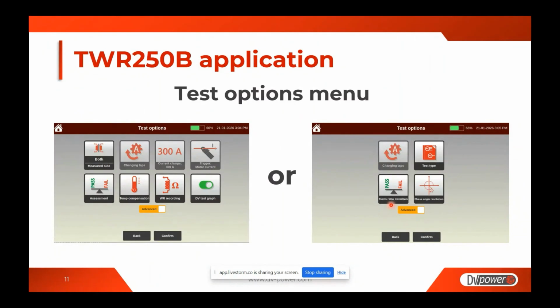On the left-hand side, you can see the display related to test options menu for winding resistance measurement, where you can select if you want to perform high voltage or low voltage winding resistance measurement. Temperature compensation is also available. So these are test options. They are related to the selected test.